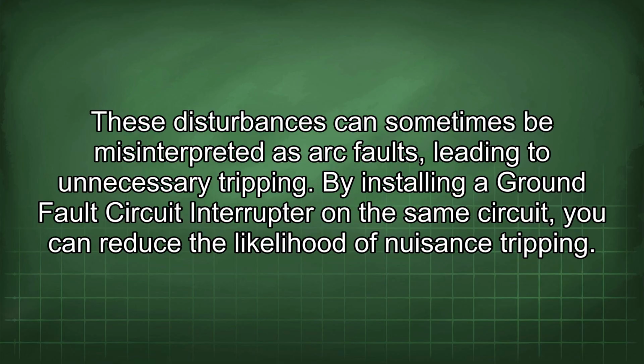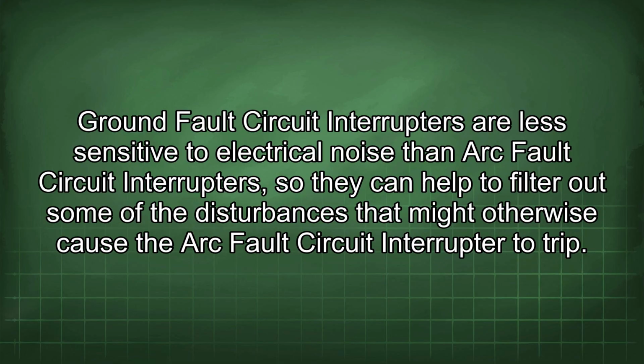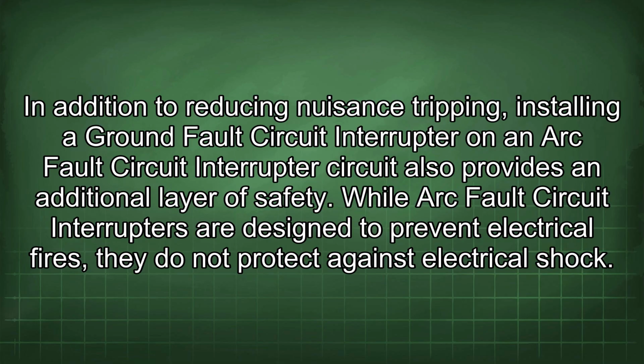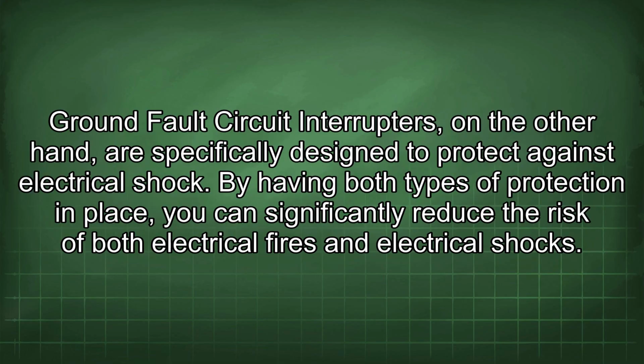By installing a ground fault circuit interrupter on the same circuit, you can reduce the likelihood of nuisance tripping. Ground fault circuit interrupters are less sensitive to electrical noise than arc fault circuit interrupters, so they can help to filter out some of the disturbances that might otherwise cause the arc fault circuit interrupter to trip. In addition to reducing nuisance tripping, installing a ground fault circuit interrupter on an arc fault circuit interrupter circuit also provides an additional layer of safety. While arc fault circuit interrupters are designed to prevent electrical fires, they do not protect against electrical shock. Ground fault circuit interrupters, on the other hand, are specifically designed to protect against electrical shock.